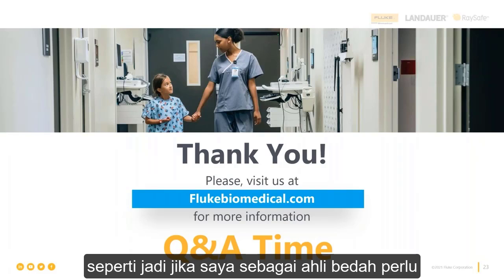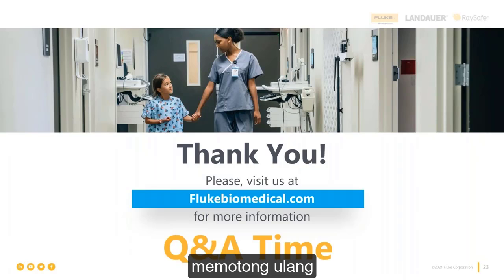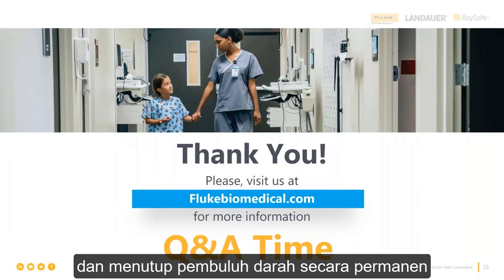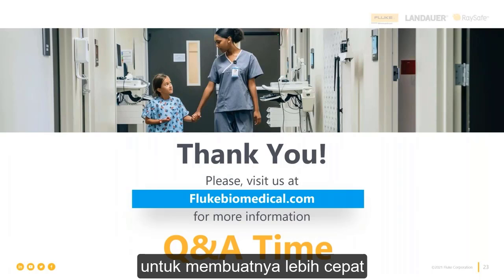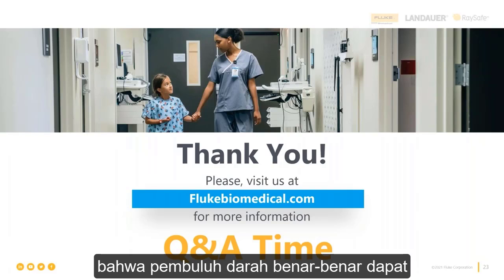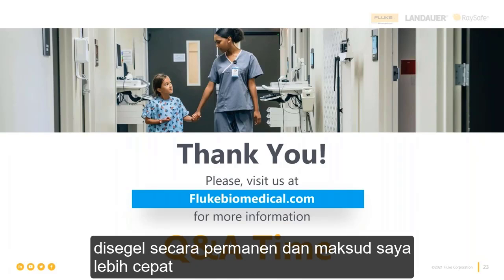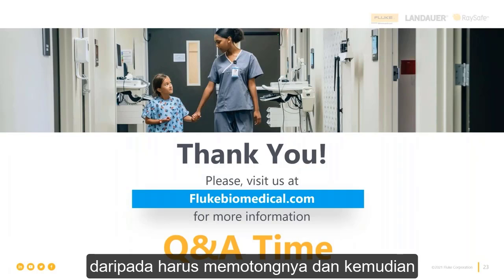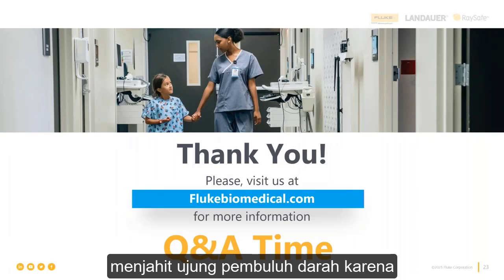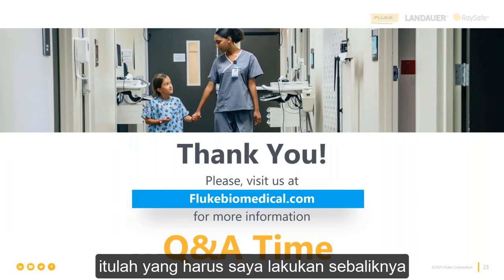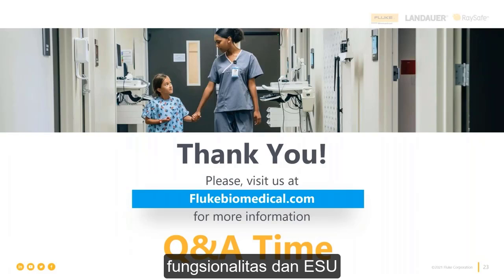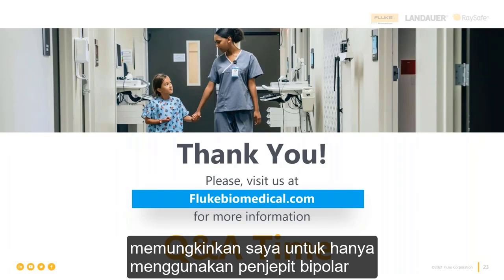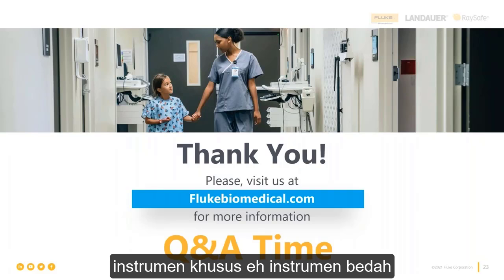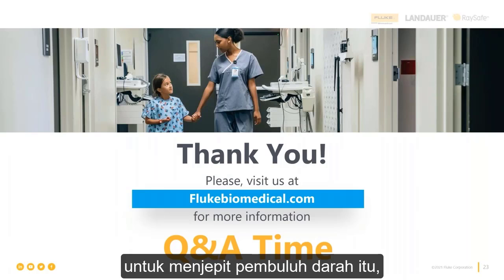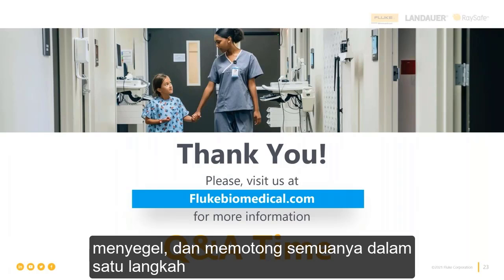So if I, as a surgeon, need to cut through and permanently close off a vessel, I need it to be faster and ensure the vessel is totally and permanently sealed, faster than having to cut it and then suture up the end of the vessel, which is what I'd otherwise have to do. The vessel sealing functionality in ESU allows me to use a bipolar clamp, a specific surgical instrument, to clamp that vessel, seal it, and cut it all in one step.